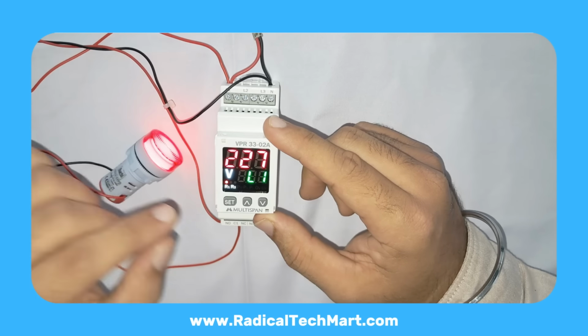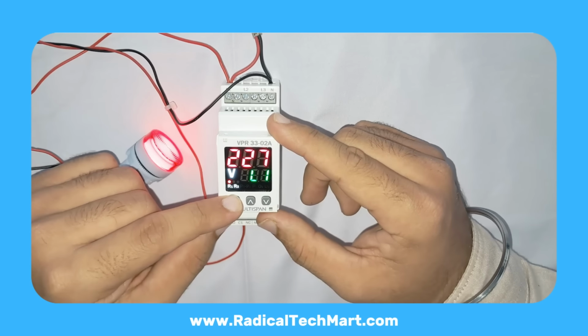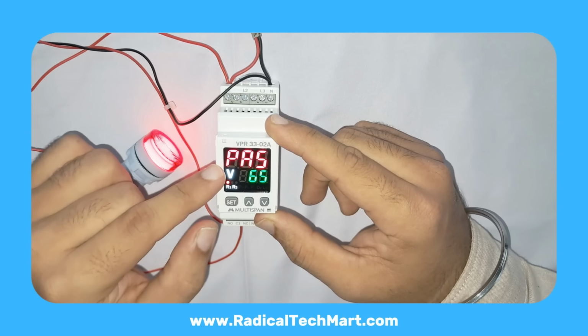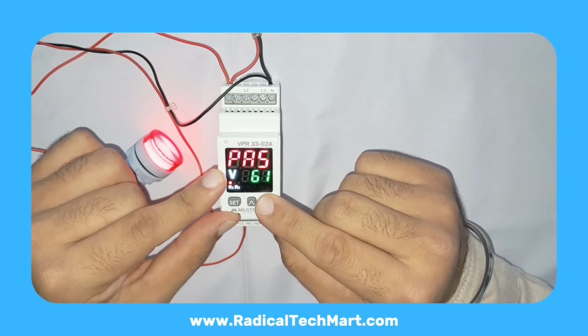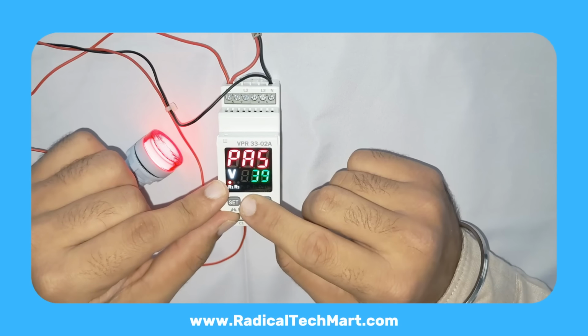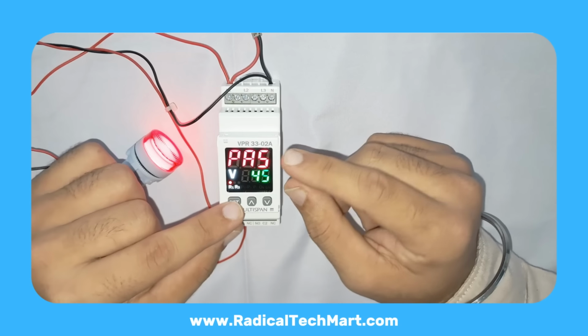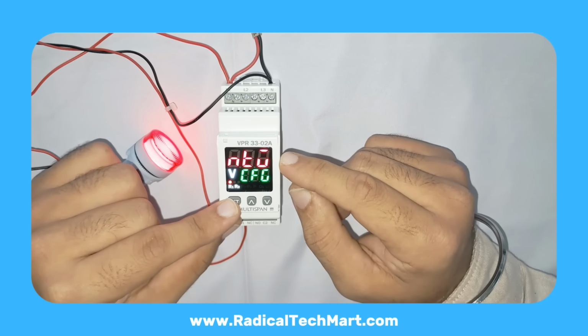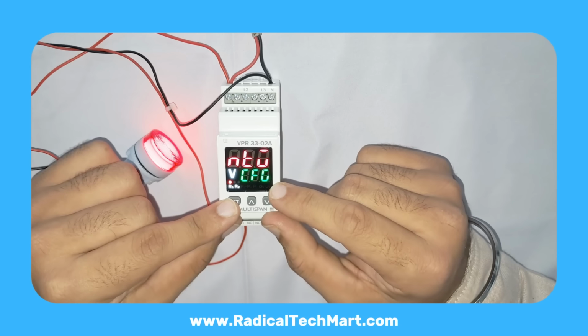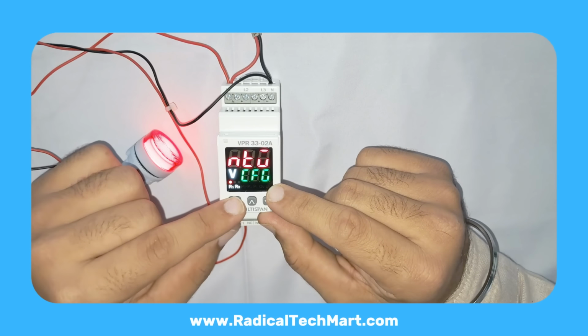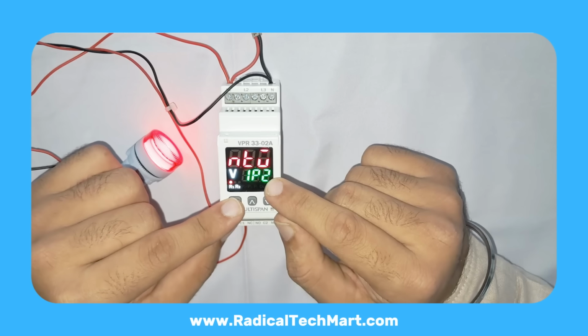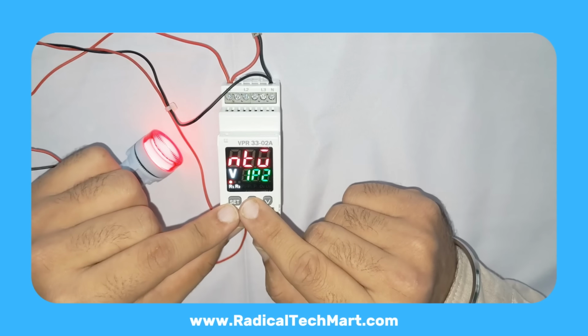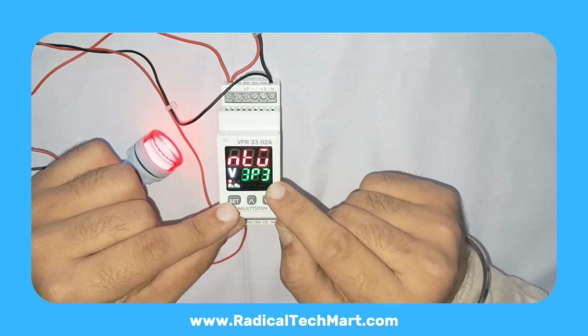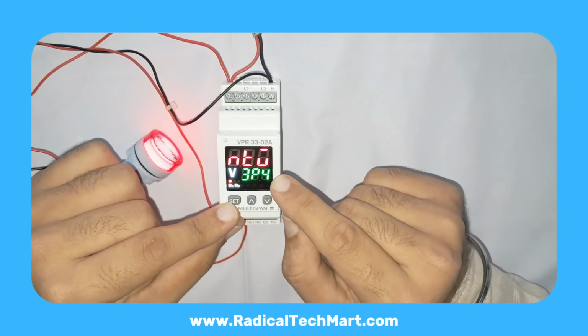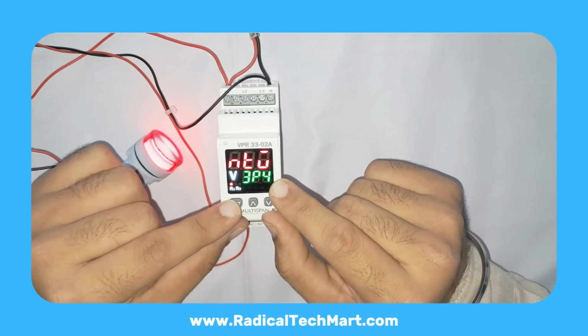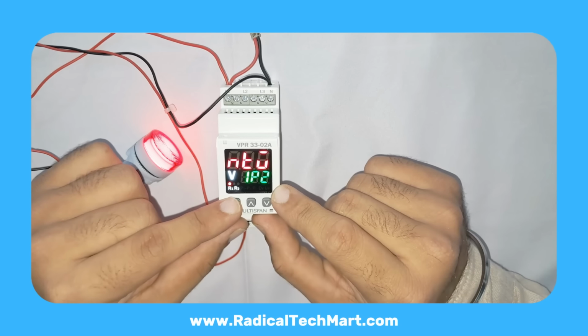Entering parameter settings. To enter the parameter settings, press and hold the set button for about 5 seconds until it shows pass. The password is 45. Set 45 using the up-down buttons, then press set to confirm. Network configuration. The first menu will be Network, and under it, CFG, meaning Network Configuration. Press Set to enter. You will now see 3 options. 1P2 single phase, 2-wire. 3P3 3-phase, 3-wire. 3P4 3-phase, 4-wire. Since we are using single phase in this demo, we select 1P2.